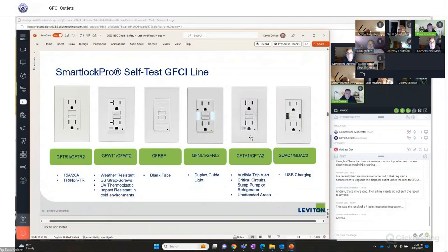This was an item that we talked about right before the meeting: what happens if you have a GFCI receptacle on an area that's unattended, like a sump pump, or behind a refrigerator, and it trips and you don't know about it? This is basically an audible GFCI. It will beep until you reset it. And same thing with all of our devices: you can see at the bottom right we've got the LED light. These are all self-test devices. When they're at end of life, you'll see a red light. You won't be able to reset it. It's time to change that out.